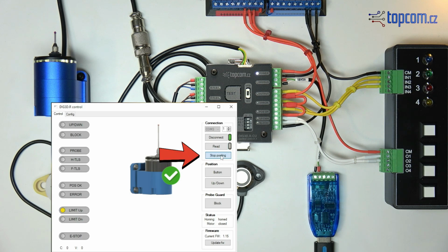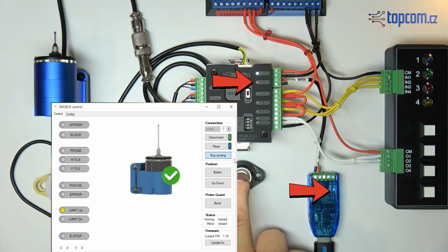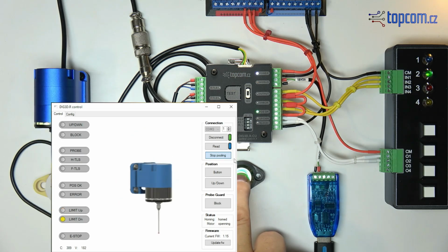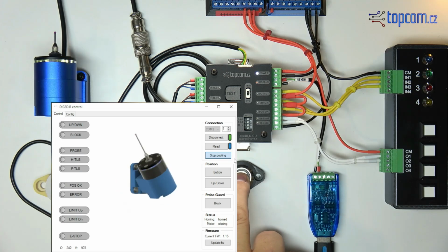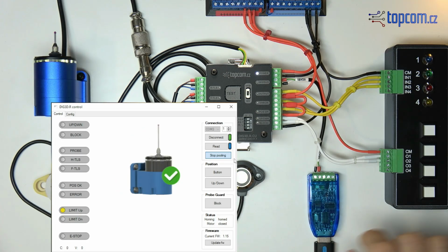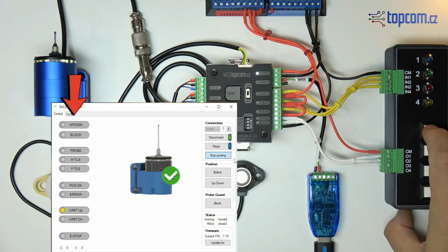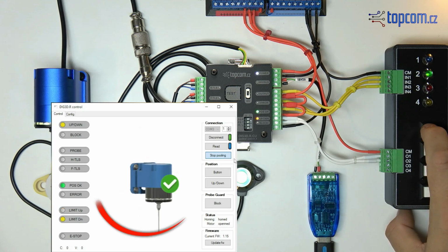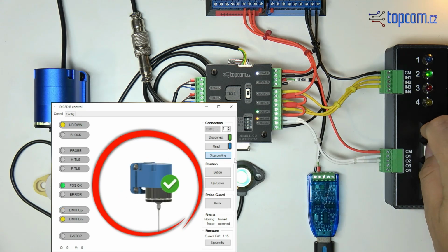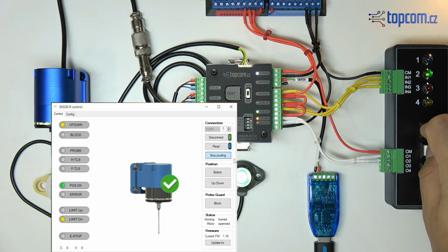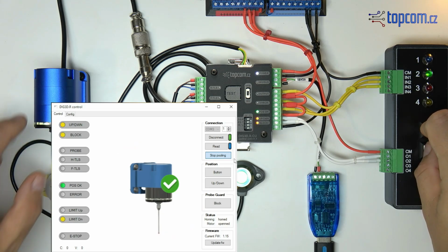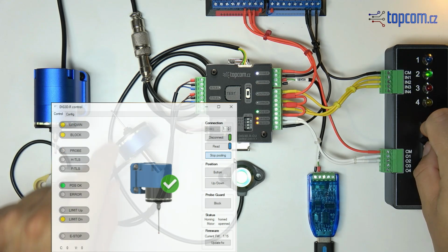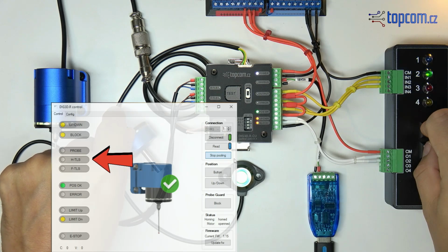If you want to read data continuously, use the Poll toggle switch. Ongoing communication is indicated both on the converter and on the control unit. In continuous reading mode, the current status is displayed in the application window. Both input and output states are transmitted, along with a graphical representation of the probe's current position. Although the signals from the probes and sensors are combined into a single output, the Modbus interface allows you to read the status of each individual input separately.